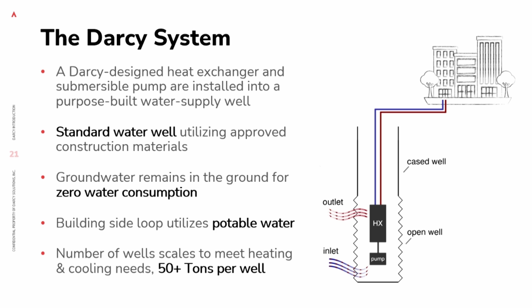This system scales. We install these wells in parallel, so any individual well can be shut off or serviced from the surface. This makes GEO a viable option for sites that don't have enough space for a geothermal solution today. Our sweet spot is the urban environment, where you can put 1, 2, 3, 4 wells on the side of a parking lot instead of having no geothermal option at all. We love traditional geothermal and pair well with other technologies, and we believe this will enable the market to grow by a factor of 10, since far more sites will be applicable for geothermal than ever before.